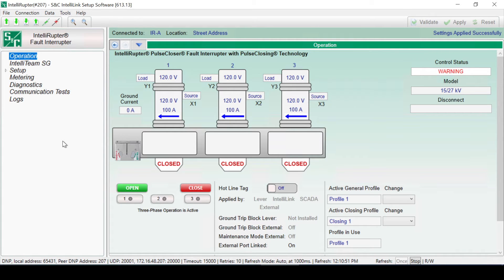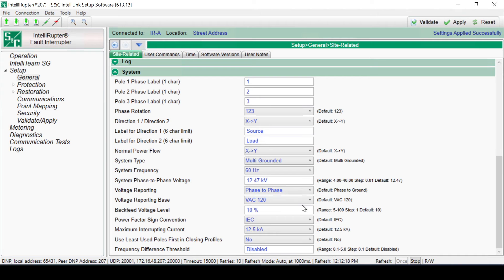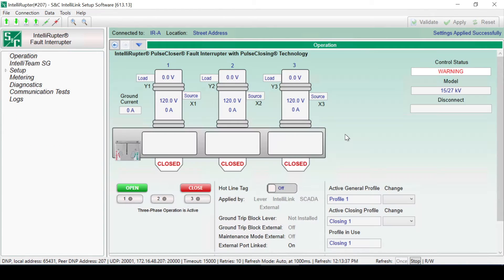Voltage Reporting can be changed here as well. When Phase to Phase is selected, Voltage Reporting will change the reporting levels by a factor of 1.73, the square root of 3, for the Operations screen, the Metering screen, and SCADA.